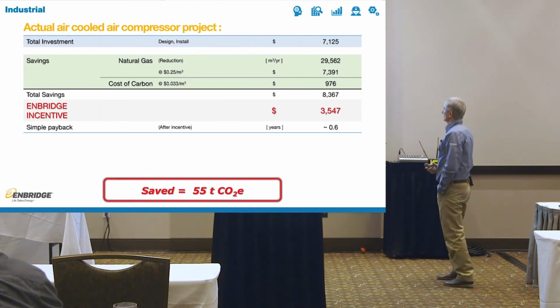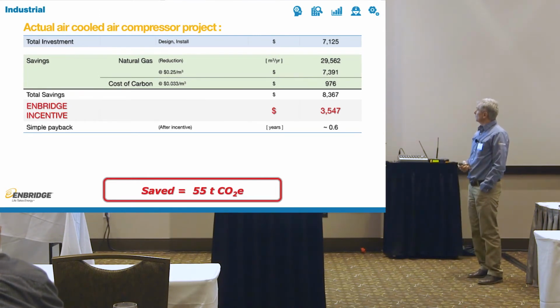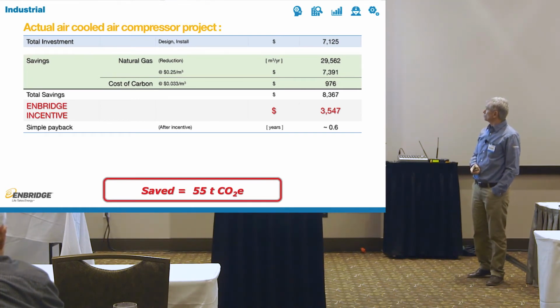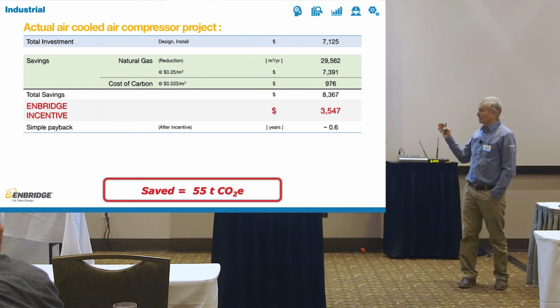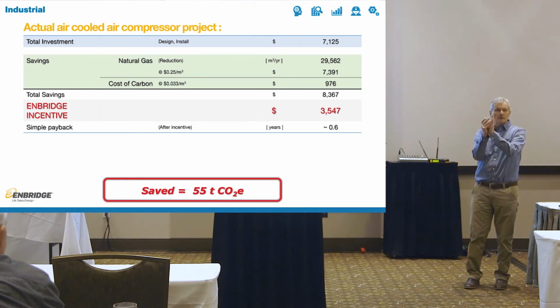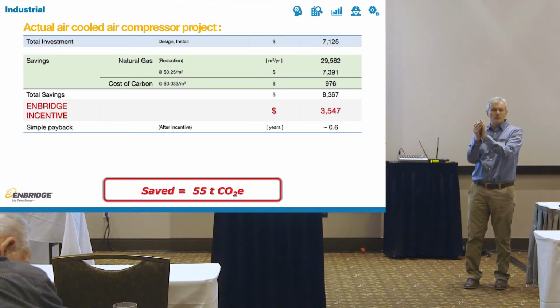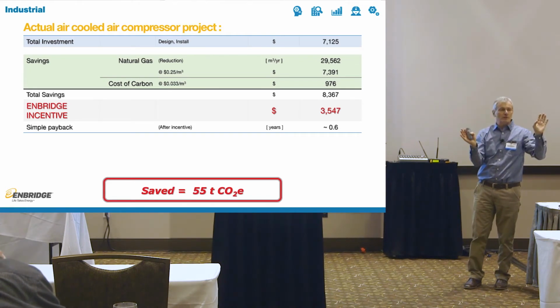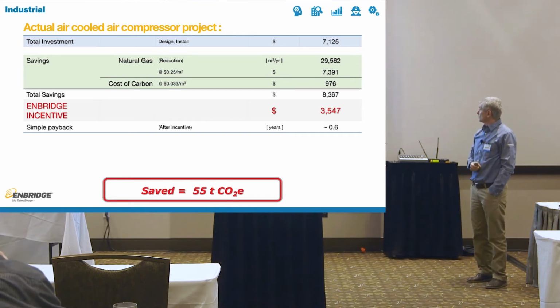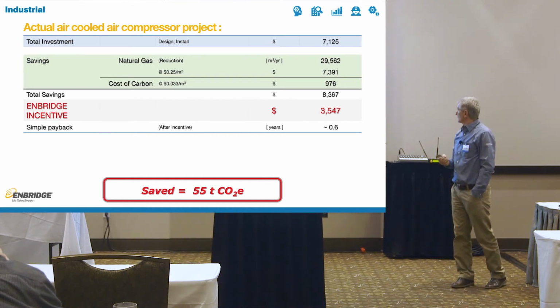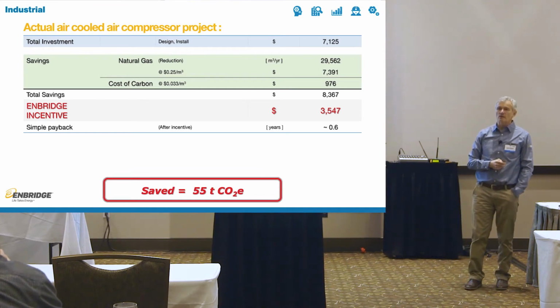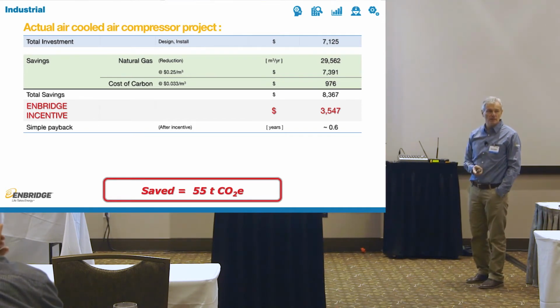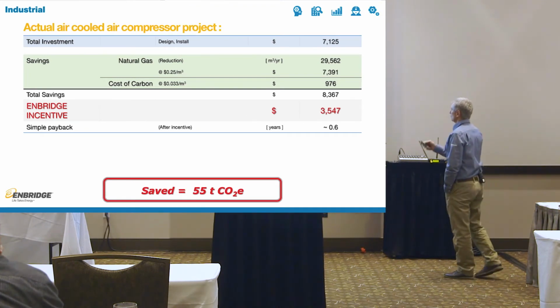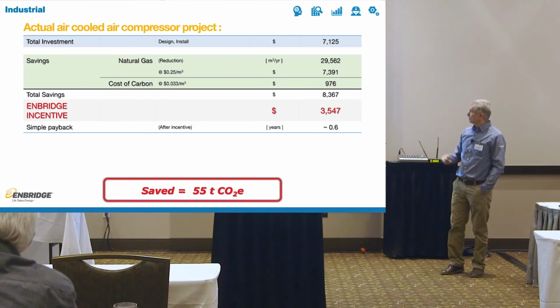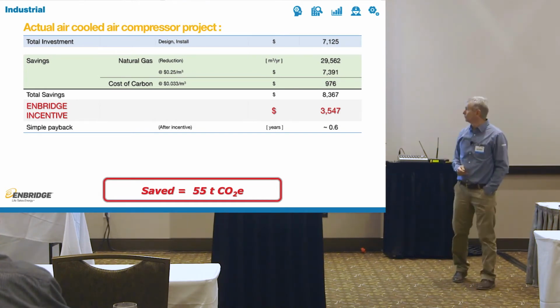So these guys spent $7,000, for about a half-year payback after our incentives, to reduce their natural gas usage by 30,000 cubic meters. They simply put in a duct and a damper that said, in the summertime, put that heat outside; in the wintertime, put it inside. They had a little fan. That was it. They recovered 30,000 cubic meters of natural gas, and they saved $8,300 every year. Simple project. No impact on production, no impact on anything. They did that on a regular workday. They also saved 55 tons of CO2e. Not a big number, but then again, the investment was small. It's a very simple, no-brainer thing to do.